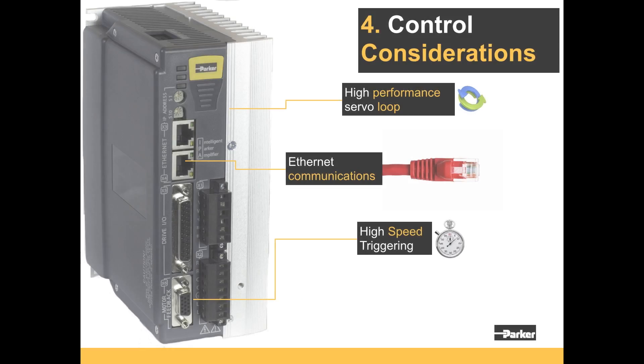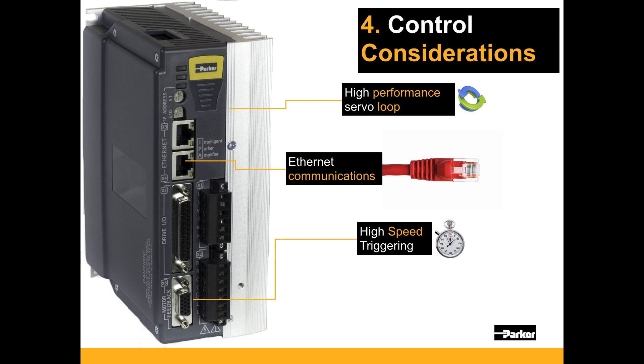Even with the best mechanics, the instrument requires high-performance controls. The control for the instrument must deliver a high-performance servo loop with advanced control algorithms and high update rate, efficient Ethernet communications between the main host PC and motion axis, and high-speed triggering that can trigger image captures from the encoder position.